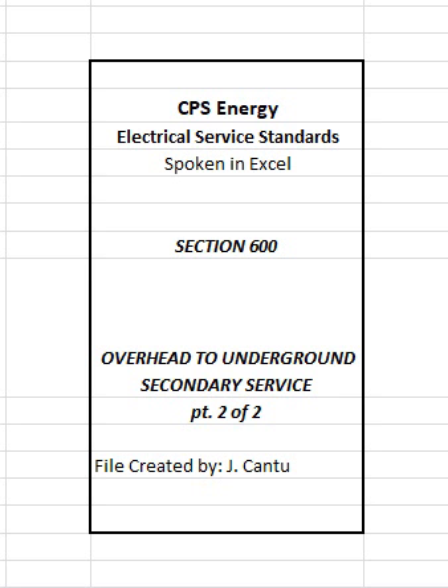605.1 Load limitations. Overhead to underground service will be limited to demand loads not exceeding 300 kVA for 3-phase and 100 kVA for single-phase, 120/240 volt service. 605.2 Conductor sizes. CPS Energy will furnish and install a maximum of 2 500 kcmil copper, 90 degrees Celsius conductors per phase for this type of service.